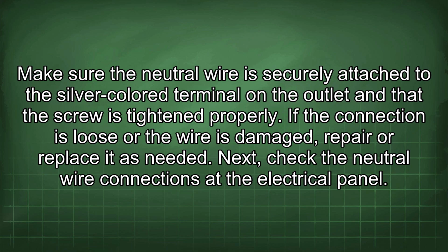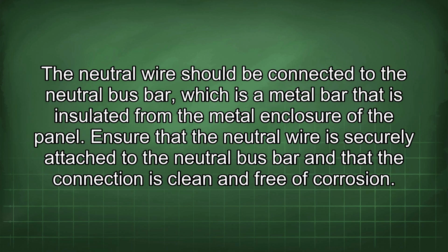If the connection is loose or the wire is damaged, repair or replace it as needed. Next, check the neutral wire connections at the electrical panel. The neutral wire should be connected to the neutral bus bar, which is a metal bar that is insulated from the metal enclosure of the panel. Ensure that the neutral wire is securely attached to the neutral bus bar and that the connection is clean and free of corrosion.